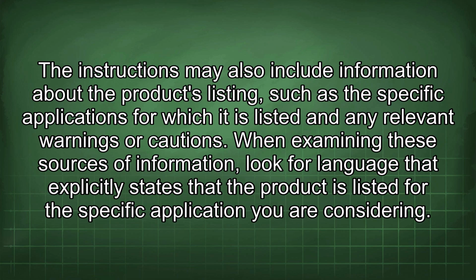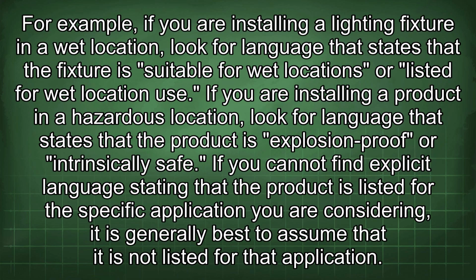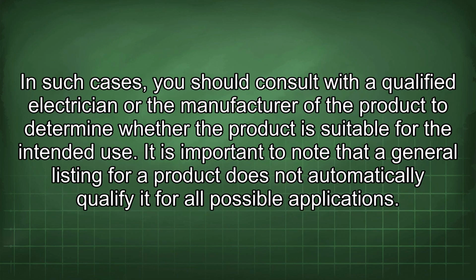When examining these sources of information, look for language that explicitly states that the product is listed for the specific application you are considering. For example, if you are installing a lighting fixture in a wet location, look for language that states that the fixture is suitable for wet locations or listed for wet location use. If you are installing a product in a hazardous location, look for language that states that the product is explosion-proof or intrinsically safe. If you cannot find explicit language stating that the product is listed for the specific application you are considering, it is generally best to assume that it is not listed for that application. In such cases, you should consult with a qualified electrician or the manufacturer of the product to determine whether the product is suitable for the intended use.